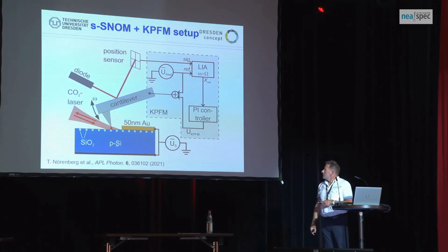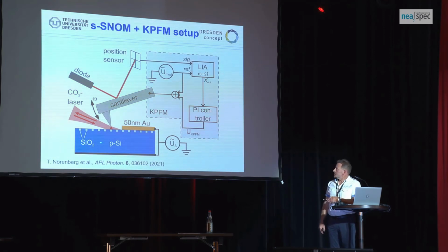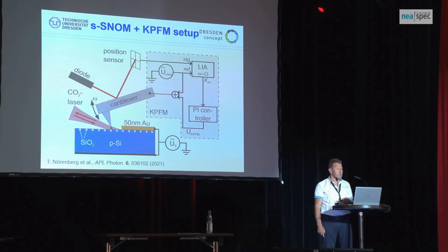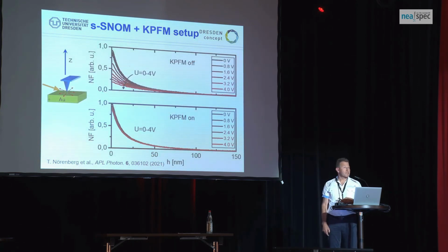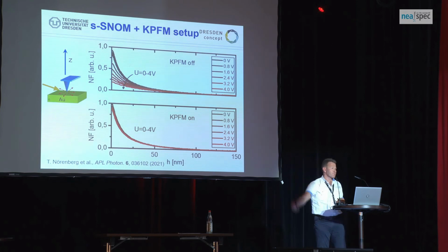parabola. As a test sample, we have been really using here a p-doped silicon substrate that has really trenches of silicon dioxide in it, and on the top of that, at one side, a gold contact in order to now flip the cantilever once on the gold contact for testing and really installing everything, and then really do measurements. Please note that we can apply also additional voltages then to the substrate for testing. Okay, first test, we go and make retract curves. That's what everybody does.